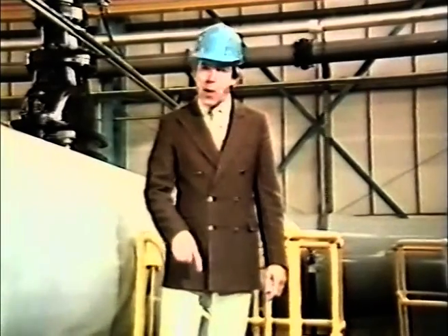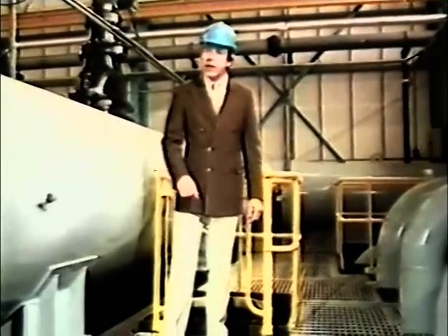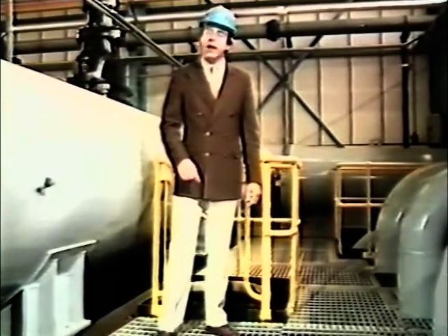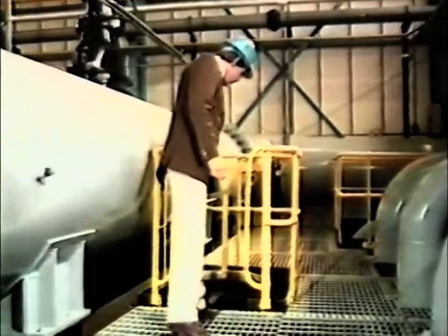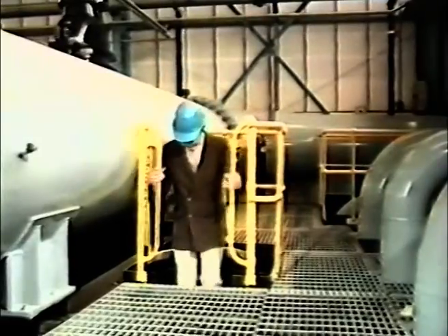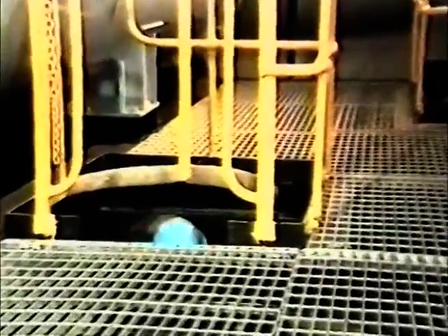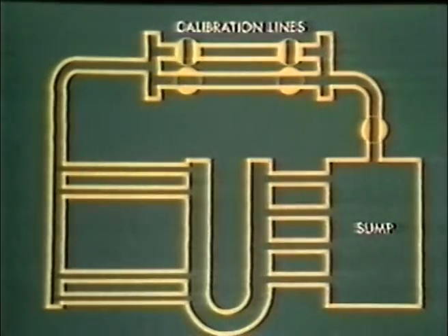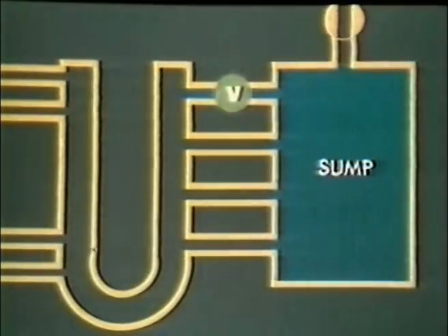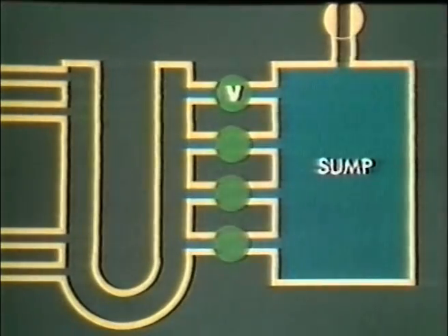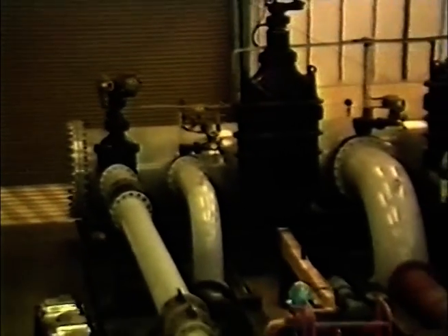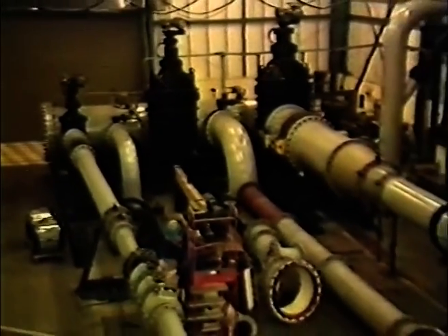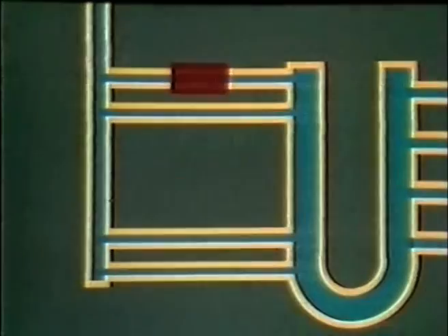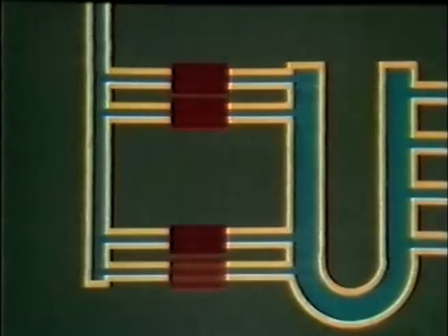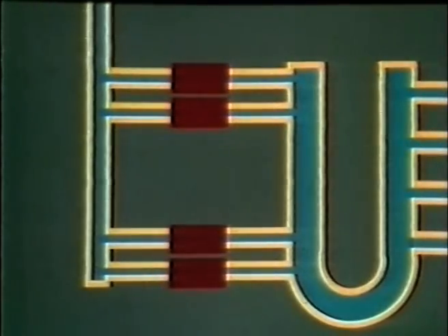Below me are 4 massive pumps, and that's the noise you can hear. Each of them can be operated either independently or in parallel. Let's go and have a look. This pump is used in every test. It's a variable speed pump, which could be used independently on a small meter or with up to 3 other pumps for a large meter. Flow rate control for the entire plant is exercised via those throttle valves. The same principle applies to the reference standard meters, which are outside. Once again, up to 4 of these extremely accurate turbine meters can be deployed in a test.